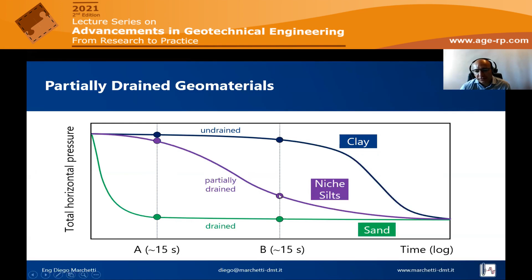So the DMT may detect this partial drainage with short dissipation tests in the first 15 seconds. If there is no appreciable drainage, you simply continue to do the standard test by taking the last reading at 15 seconds and then go to B.